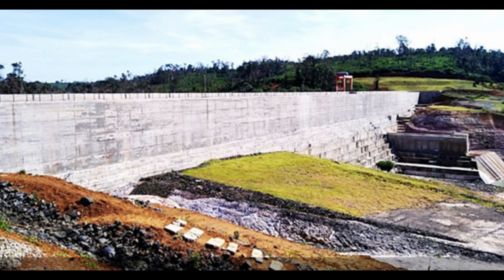So when there is load rejection, there will be a sudden backwater pressure in the tower, but it's normal, not serious. Our design is to accept that, so it's no problem. You don't need a long time to reset the system? No. Even 10 minutes we can restart.